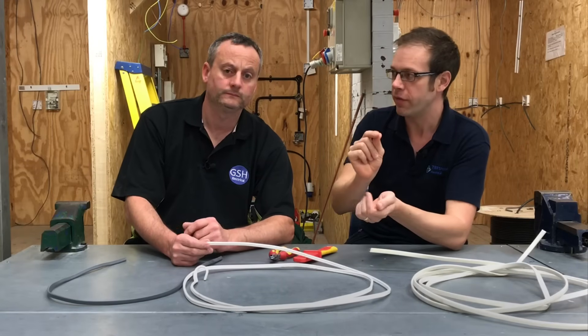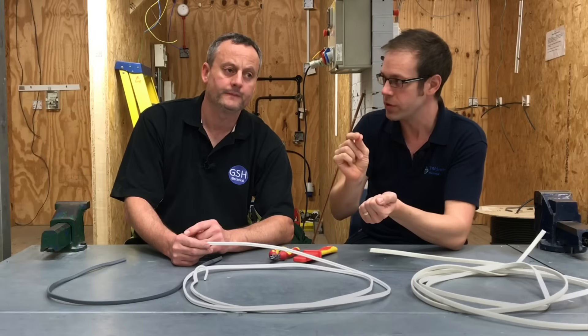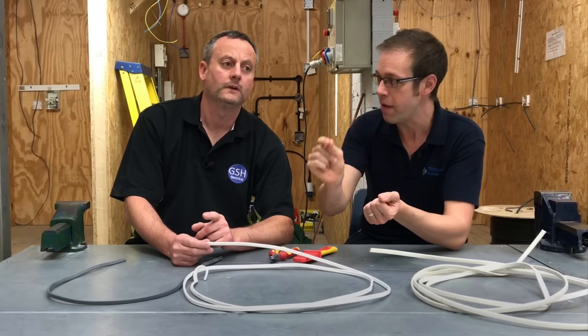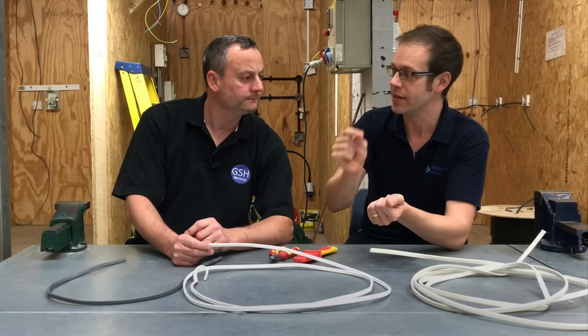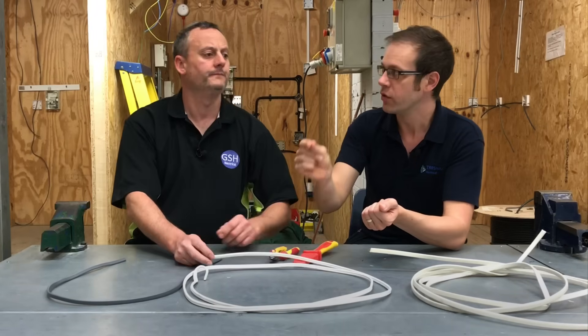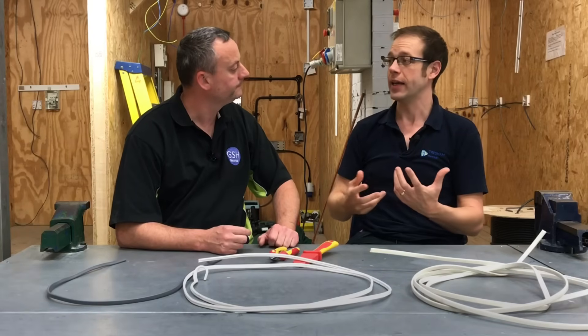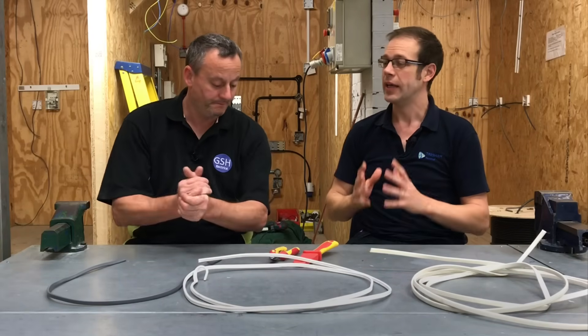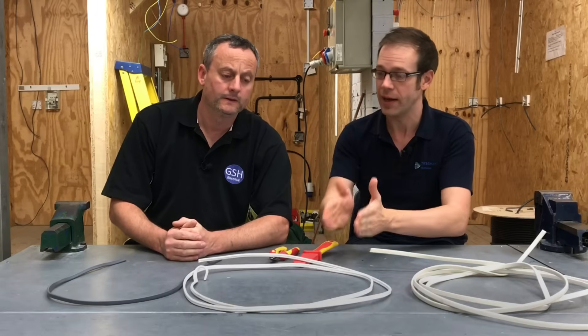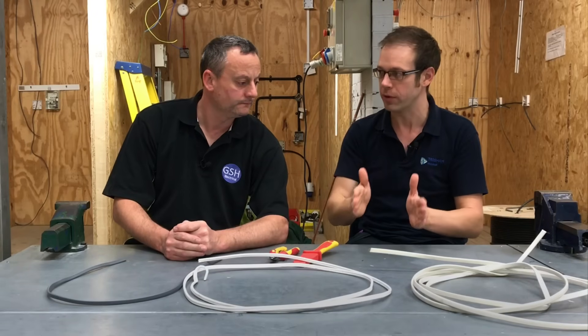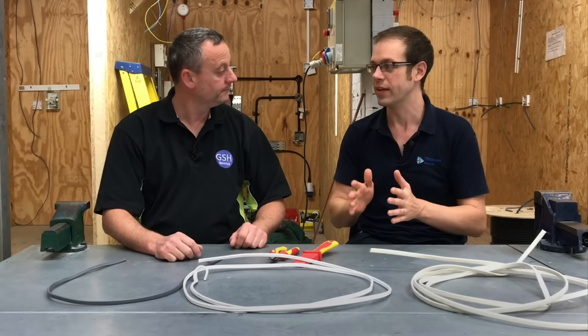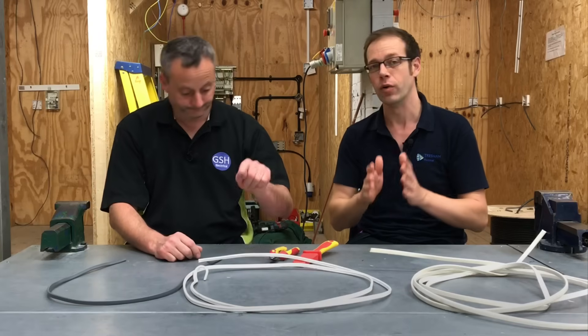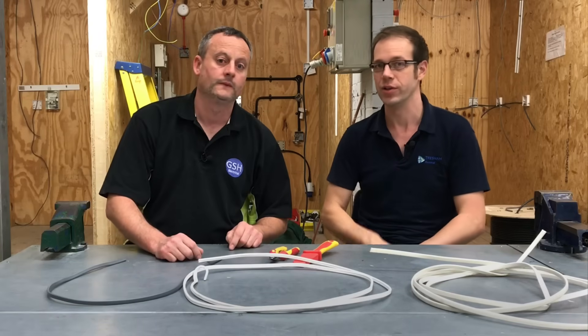The thing you've got to be really careful about is that there is a difference between LSF cable, which stands for low smoke and fume, and low smoke and zero halogen cable. So low smoke and fume cable is not strictly regulated and it can still give off dangerous gases. Whereas low smoke, zero halogen cable has to meet very strict requirements for the emission of hydrogen chloride, that halogen gas, and the smoke that it emits. So don't be tricked into thinking that low smoke and fume is the same as, or as safe as, low smoke and zero halogen. It's not.